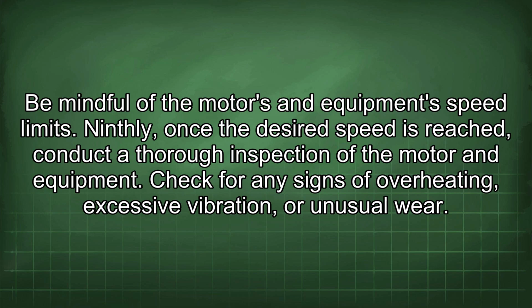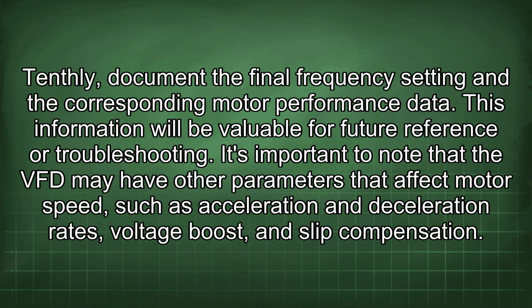Ninthly, once the desired speed is reached, conduct a thorough inspection of the motor and equipment. Check for any signs of overheating, excessive vibration, or unusual wear. Tenthly, document the final frequency setting and the corresponding motor performance data. This information will be valuable for future reference or troubleshooting.